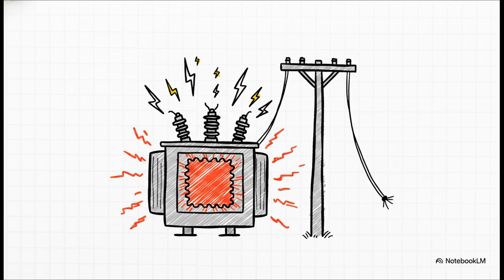Once that happens, you get these incredibly spiky AC waveforms and extra electrical harmonics that completely confuse protective relays, causing them to suddenly trip power lines. Even worse, the saturated core causes catastrophic thermal overheating. We're talking literally melting the copper coils right inside the transformer.